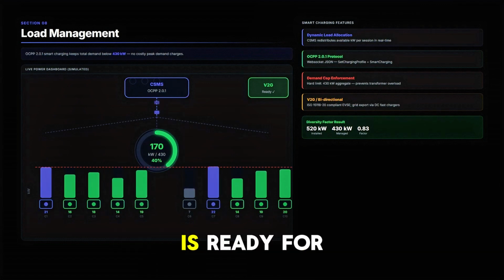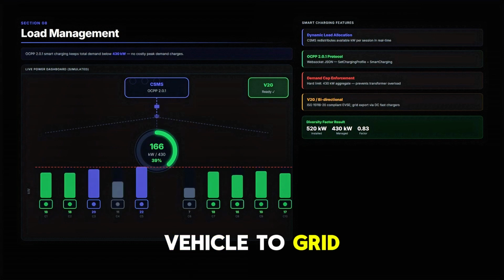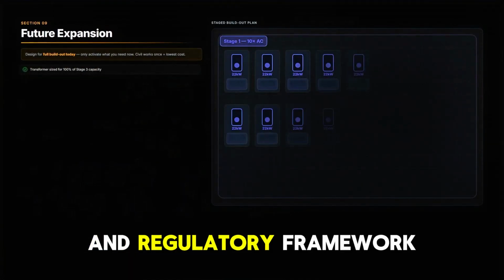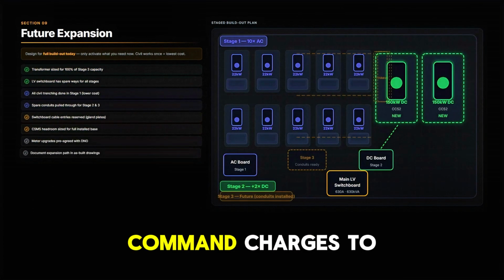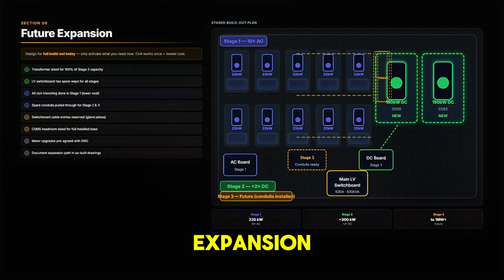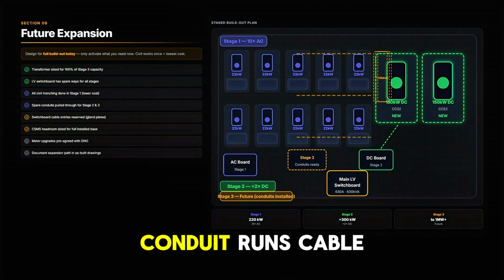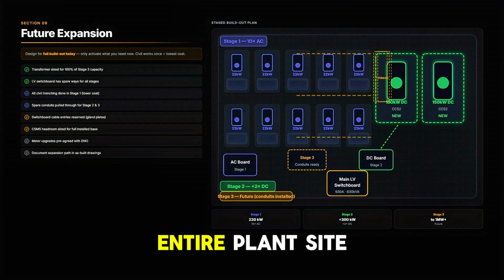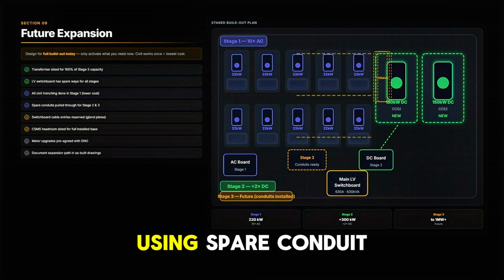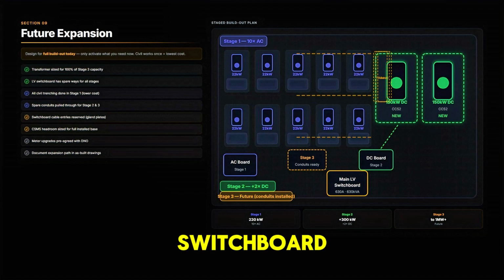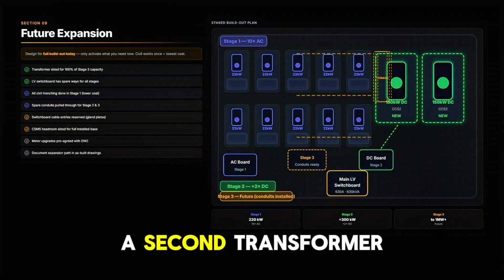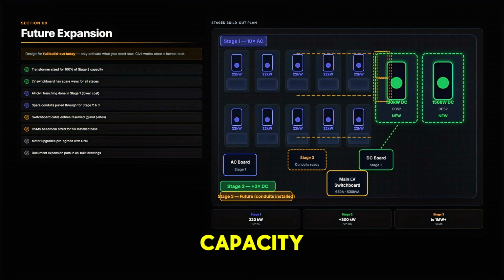The same infrastructure is ready for vehicle to grid when the technology and regulatory framework matures. The CPMS can command chargers to export power, future expansion, design for it now or pay twice later. Stage 1, we're installing now all civil infrastructure, conduit runs, cable trays, and pit systems for the entire planned site. We activate 10 AC chargers and 2 DC fast chargers. Stage 2, additional chargers. Using spare conduit sleeves and spare ways in the switchboard. No new trenching, no transformer upgrade at this stage. Our 630 gives us headroom. Stage 3, if demand grows to warrant it, a second transformer or an upgrade to a higher capacity HV supply.